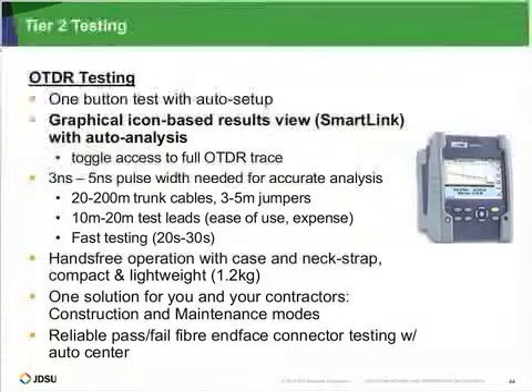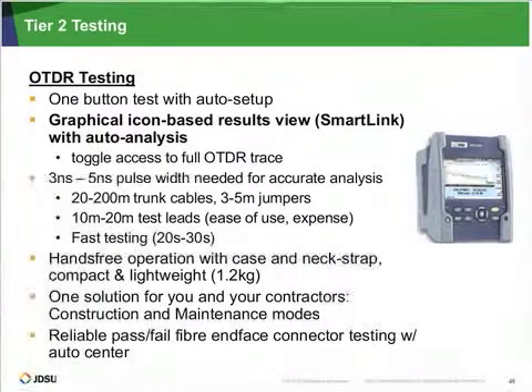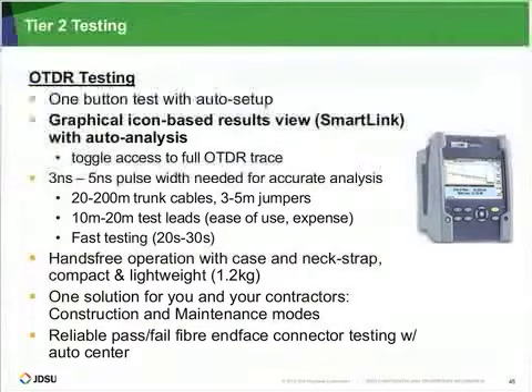You've got a light source to do round-trip loss, a visual fault locator to confirm fiber continuity, and cleaning tools and test tips for the LC connector. Then tier 2 testing is basically the OTDR. You'll typically use the smart link function if someone is inexperienced with OTDRs, or toggle across to the full trace. You need a fairly short pulse, 2 to 5 nanoseconds. Trunk cables are quite short, so you'll need some 10 to 20 meter test leads to look at the front connector and the back connector.